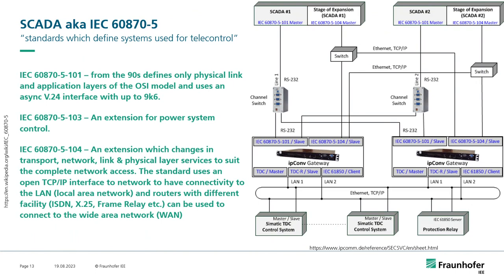At the moment, most systems use SCADA, and many of them use the IEC 60870-5 standard. This is quite an old standard, from the 90s, and it's basically a serial connection with data transfer rates of up to 9.6K. So we're basically running our whole energy infrastructure with a serial cable.